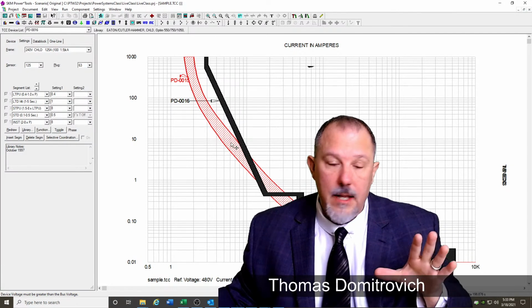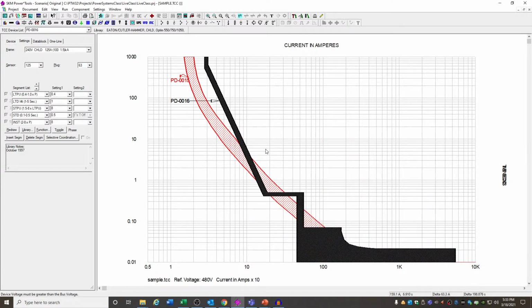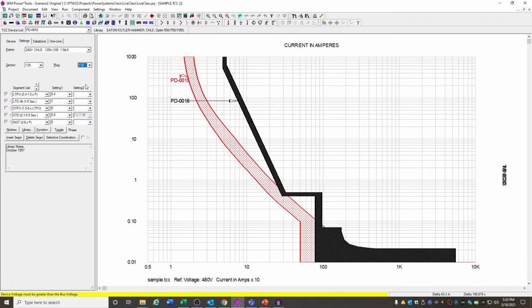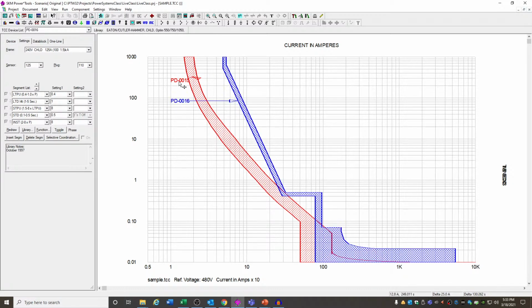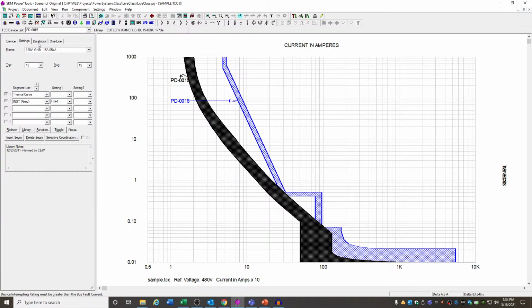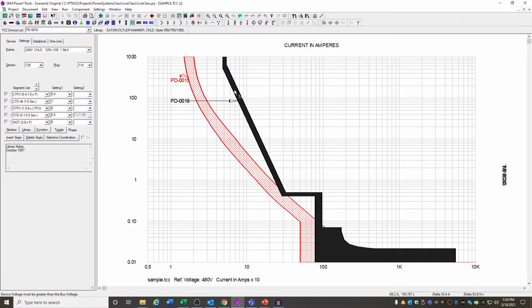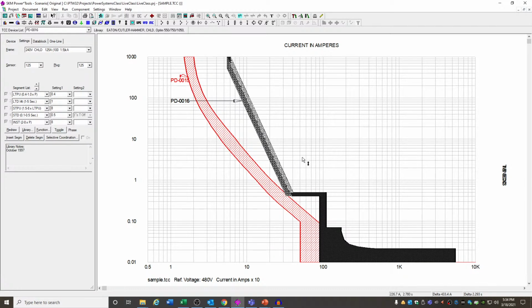Okay, so look at the way these lines are. The instantaneous region is down here on the bottom. These curves are, this is 125 amps, so that's a 63 amp. So what did I have? A GHB. What's the amp on that GHB? The GHB is a 15 amp. So on this one here, I'll make him 125 amps, and I'm going to add some delay, or let's even increase it a little bit higher.